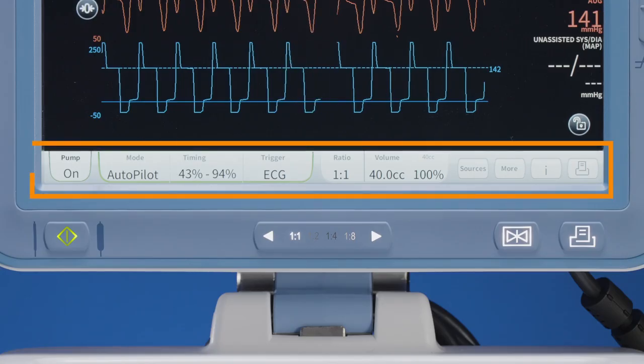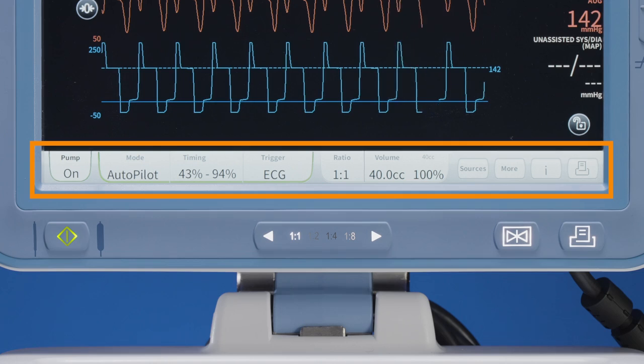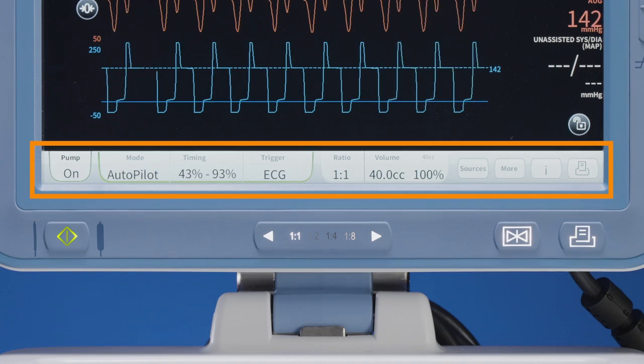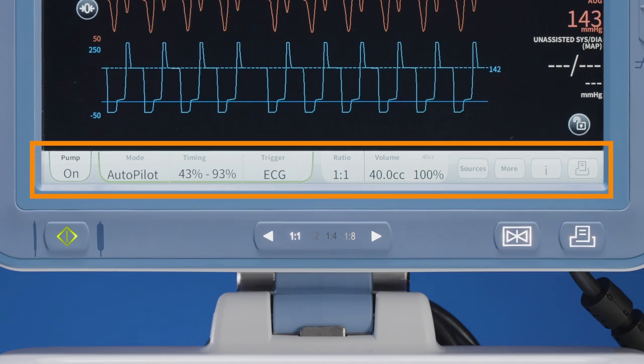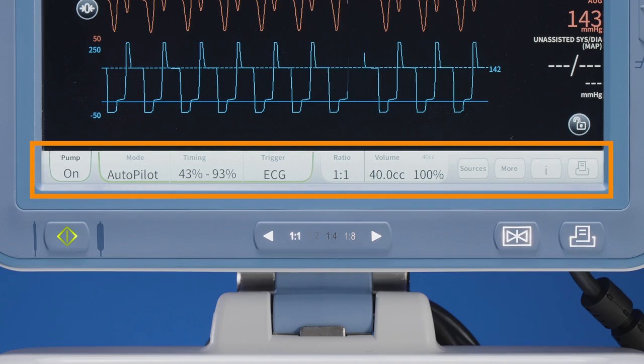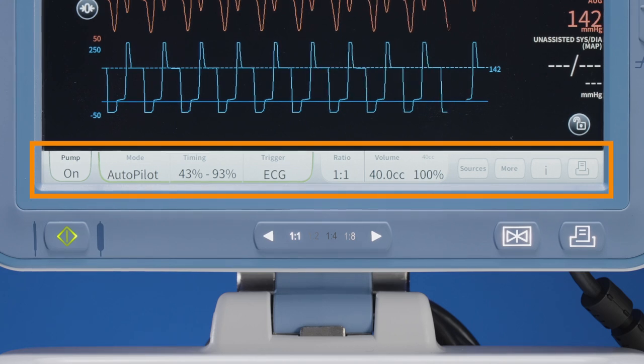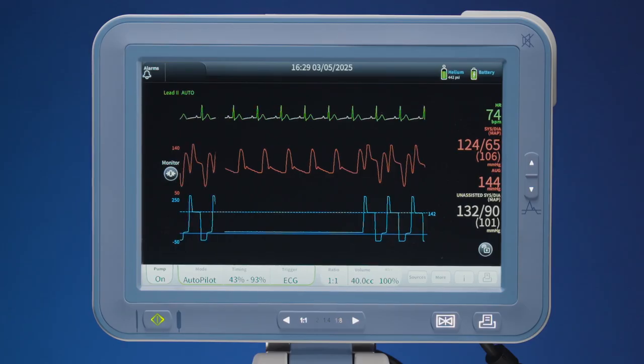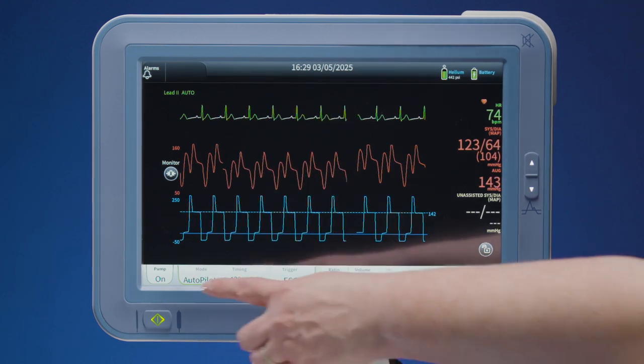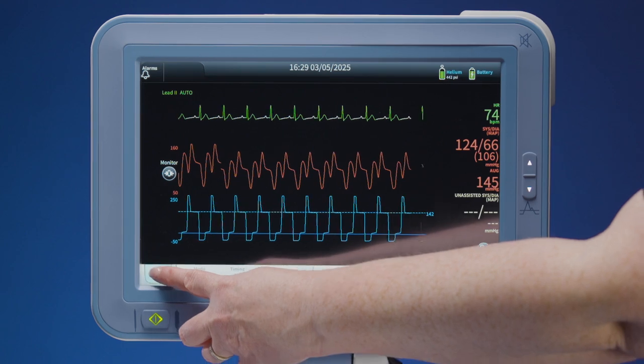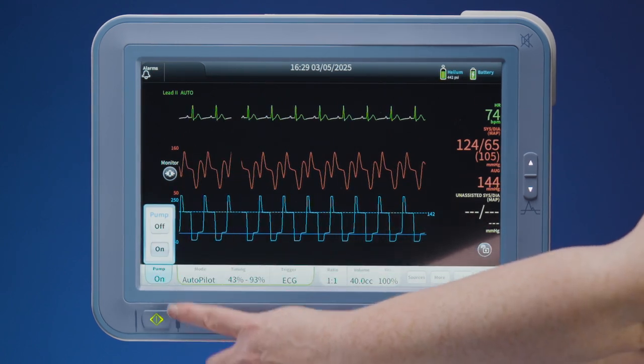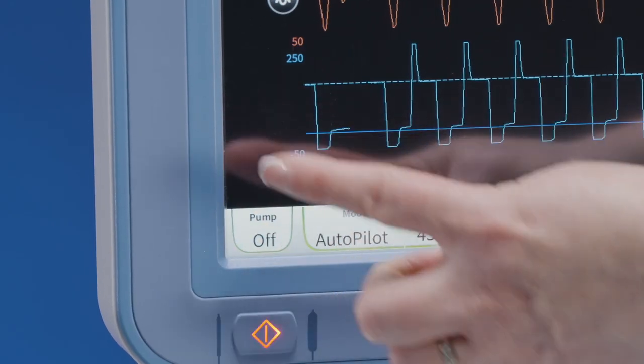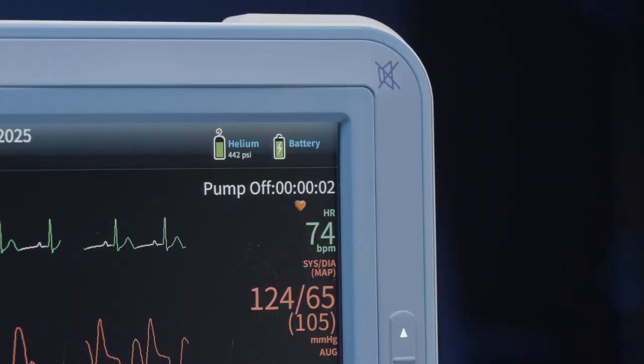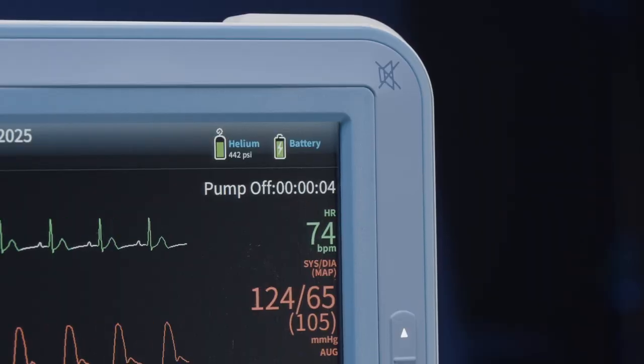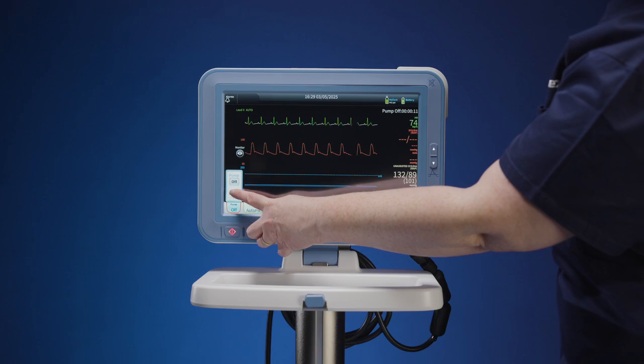The action bar is the main operations menu. The action bar combines the assessment point for IABP operations with the control for changing IABP operations or settings. The controls related to IABP therapy include Start-Stop pumping. Note, the user can also start and stop pumping by pressing the hard key on the display control head. Anytime the pump stops pumping, a timer will start and show how long the pump is off.